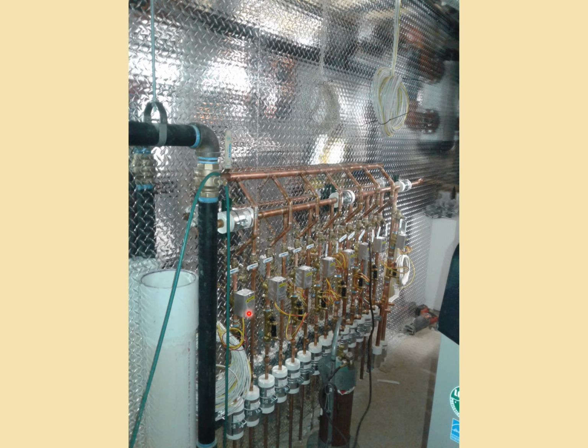It could be baseboard heat or in-floor radiant heat, and it could even be different loops in the same room, though not generally. Typically it's just different rooms, different spaces. What makes hot water heat so nice is that it's a radiant heat, heating the objects in the room rather than the air, but it heats very slowly. Once it reaches temperature though, it's very nice and stays consistent, not taking a lot to keep warm, because if it's in-floor radiant heat, it's heating up the floor, especially if it's in a layer of concrete. That concrete becomes quite the heat sink, heating up that thermal mass.